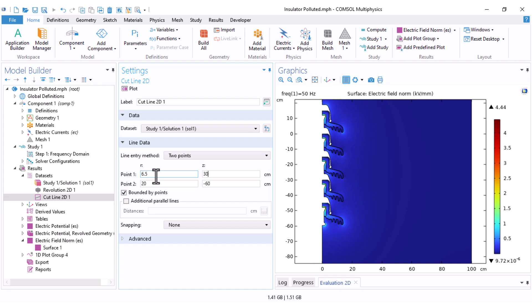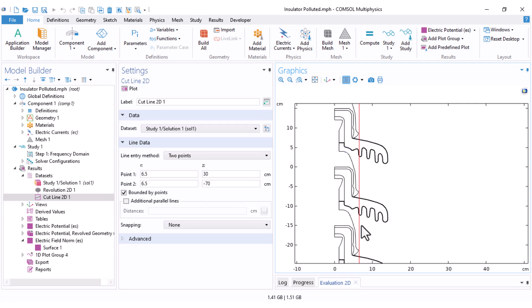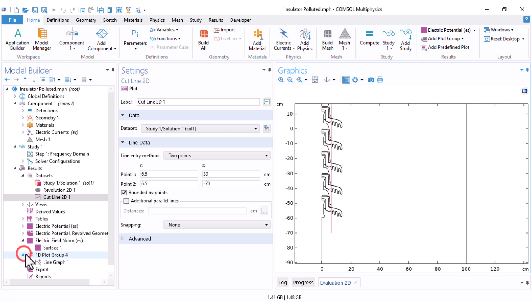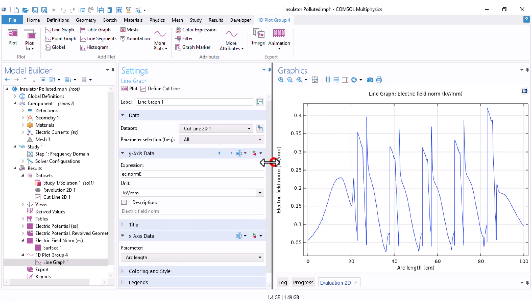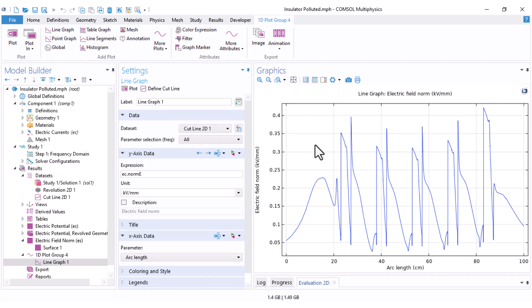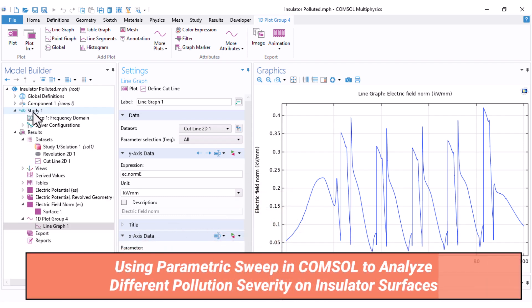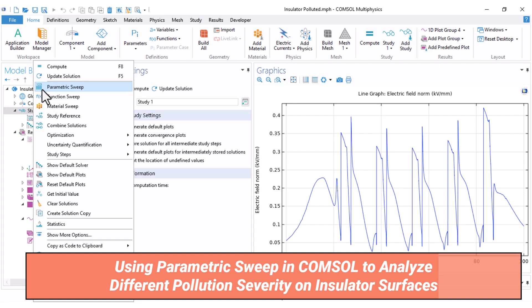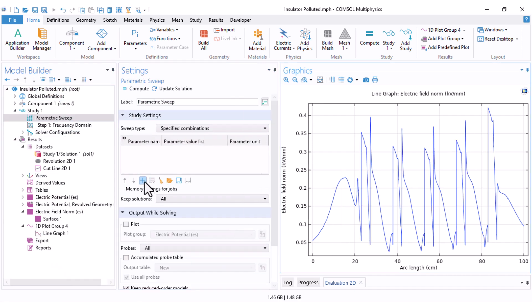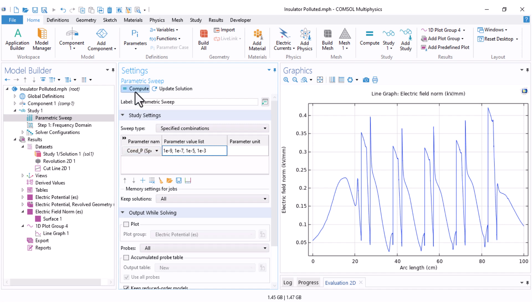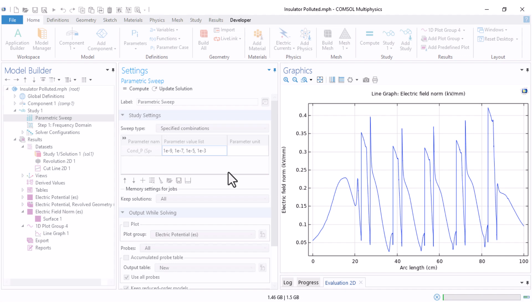In the dataset I adjust the cut line options, defining the cut line near the cap geometry. I change the electric field expression to 'ec.normE' and set the unit to kilovolt per millimeter to display electric field distribution along the insulator. To see the effect of the pollution layer I set up a Parametric Sweep under Study. I add the conductivity_p parameter and set the values from 10 to the power of minus 9 to 10 to the power of minus 3, then compute the model.